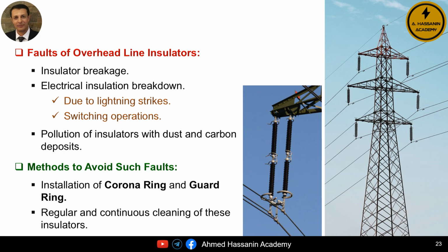Therefore, it is very important to pay attention to the installation of corona rings and guard rings, and in a separate lecture we will explain the difference between them. It is also essential to carry out regular and continuous cleaning of these insulators to prevent the accumulation of dust or salts, thereby avoiding any partial discharge or flashover from occurring.